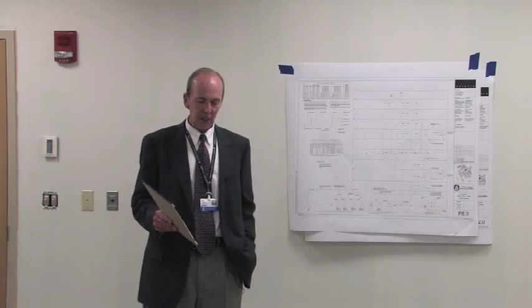Life safety is one thing, critical is different, but that's priority 1 loads. Life safety and critical are both priority 1 loads. But there's nothing that says you have to have only 1 machine for priority 1 loads. I know that's what everybody likes to do, but you've got 4 machines down there. So if you needed to go into the second machine for your priority 1 loads, that's not the end of the world. Everybody says priority 1, but if you've got 4 generators, you've got 4 priorities.